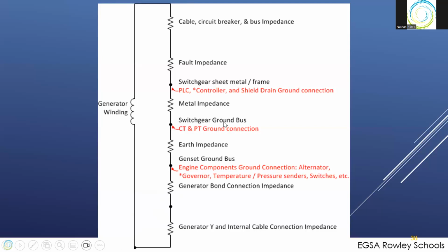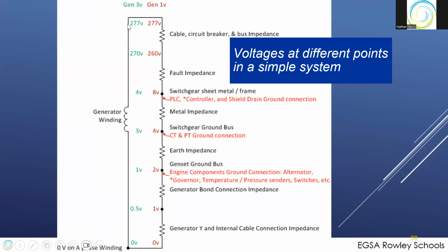And when we have this high fault current flow, we'll make up some voltages and put them in here. Gen 1 is closer than Gen 3. They're both generating 277 volts. Because Gen 1 is closer, we're going to say that there's more current flow. So here it's 260 instead of 270 volts because we're dropping more voltage with more current through here. The voltage difference here is due to the different amount of current flowing in Gen 1's phase A path versus Gen 3's phase A path, and it causes a differential.